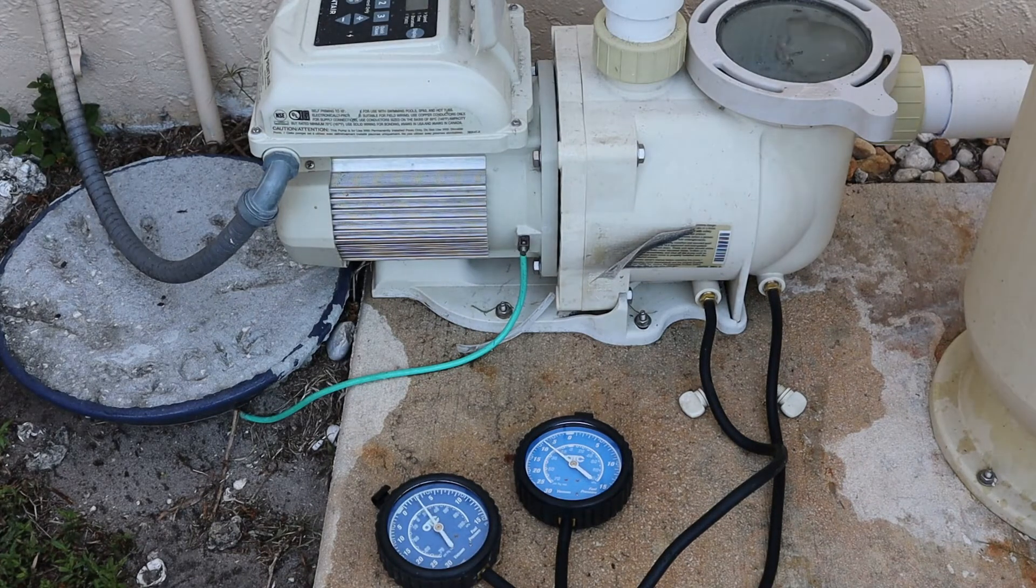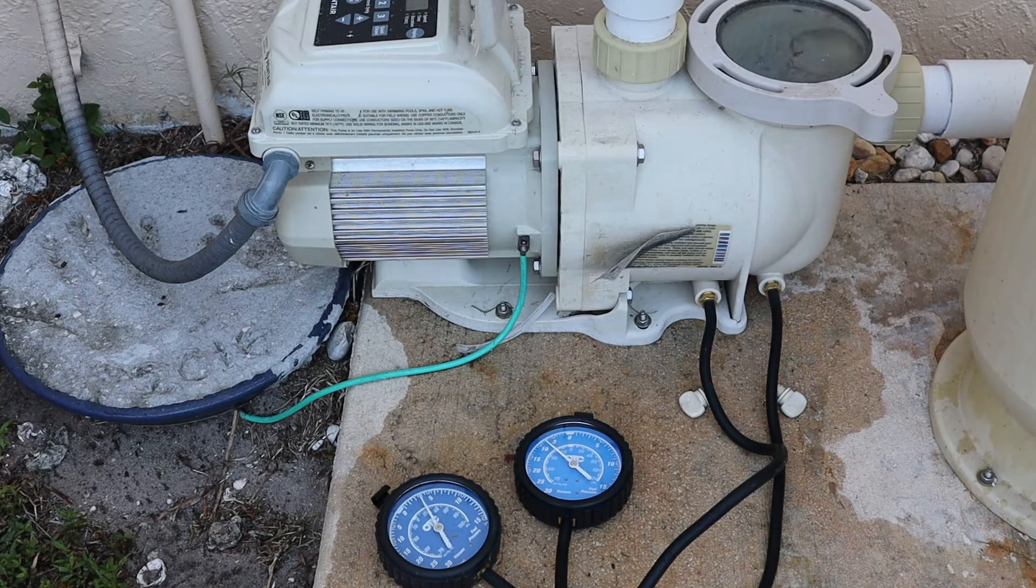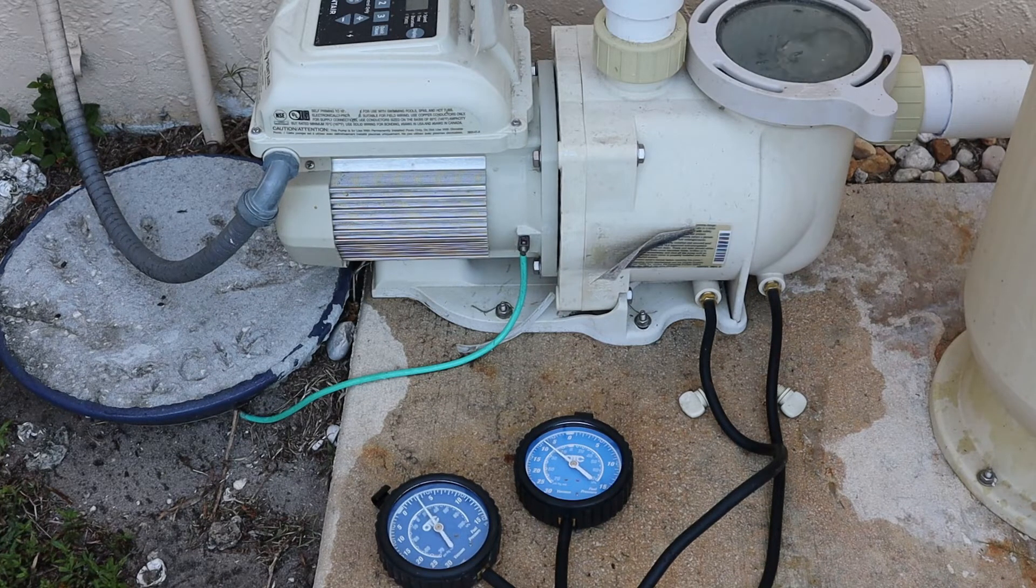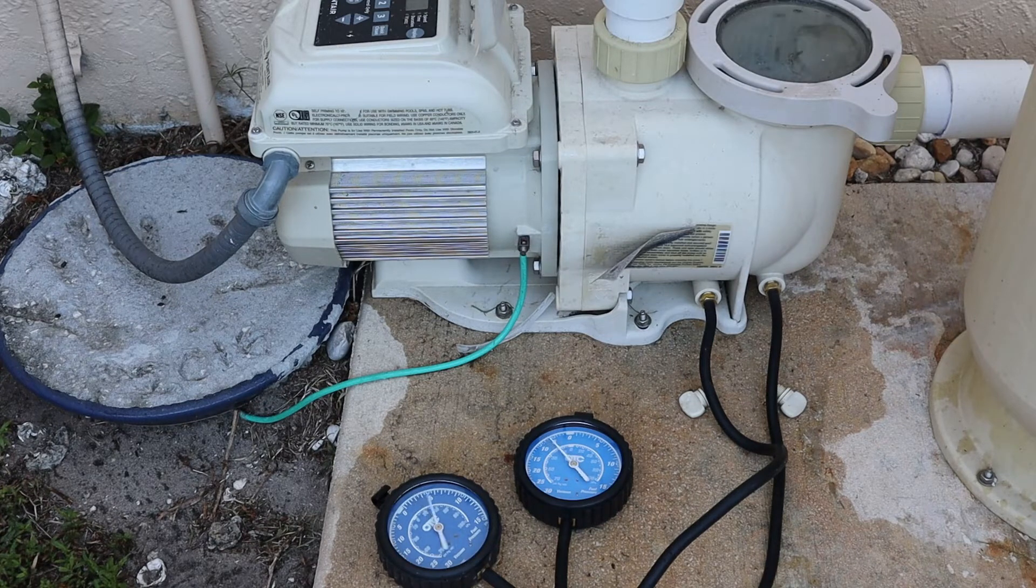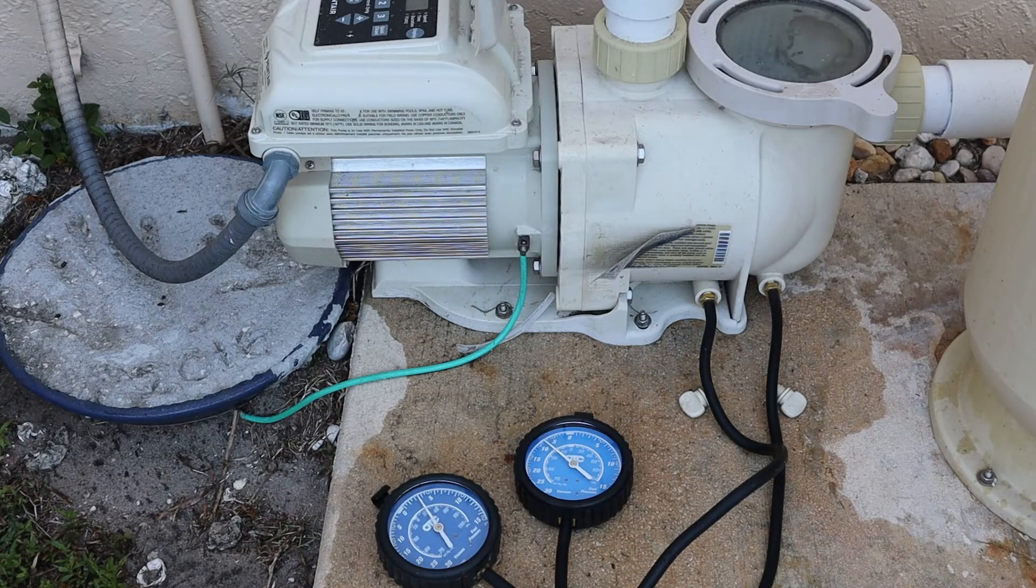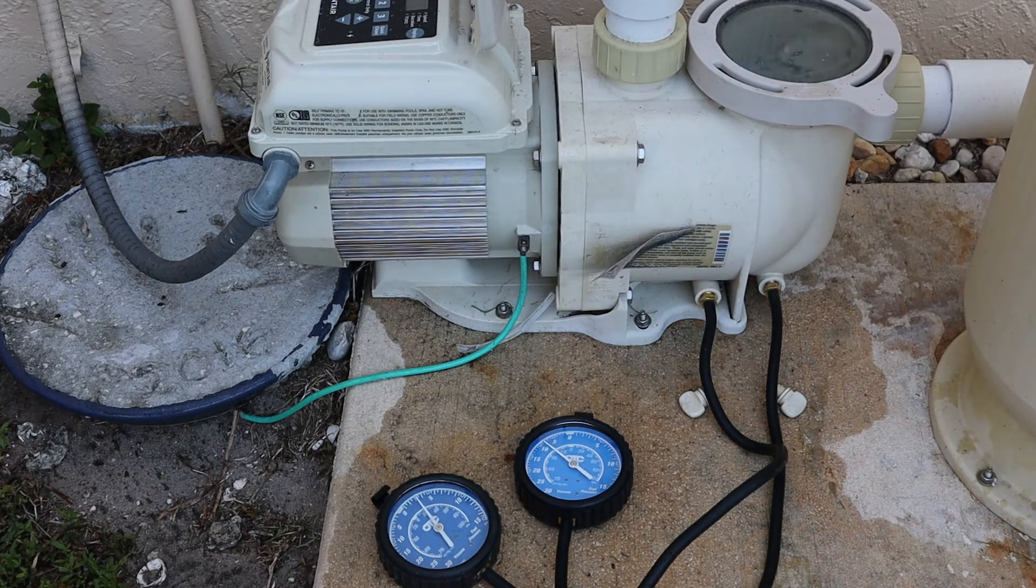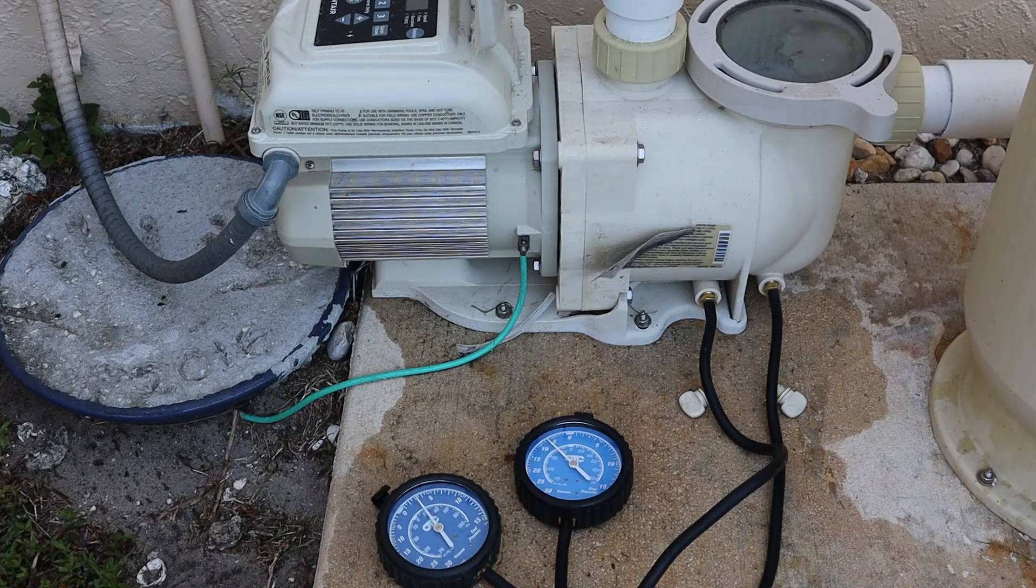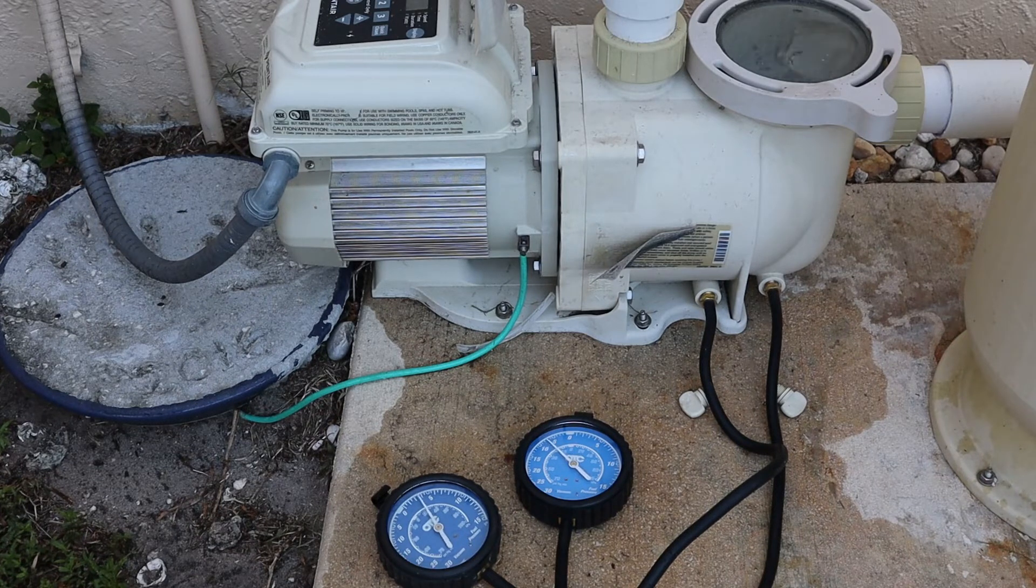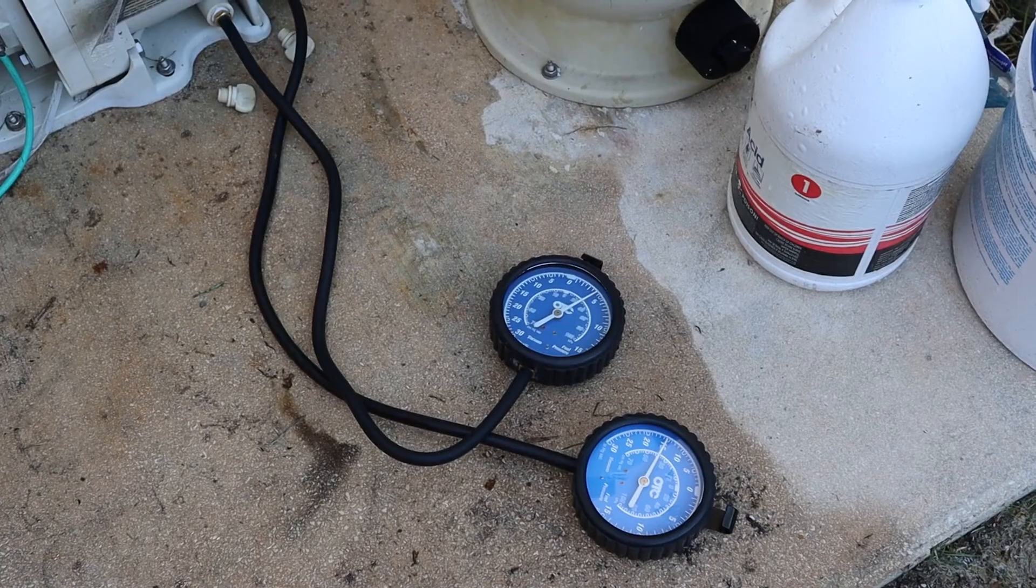I'm going to record those measurements in an Excel spreadsheet. I'm going to vary the pump RPMs and collect measurements at various RPMs. I'll show you the end result. This Excel spreadsheet will chart the pressure and vacuum and calculate total dynamic head. Let me take these measurements first.